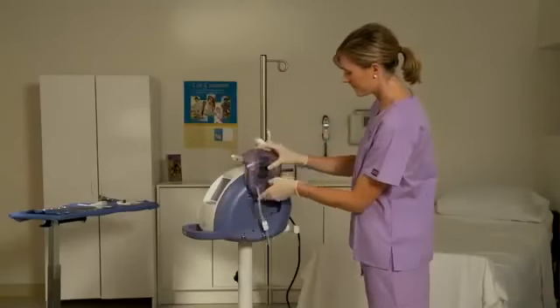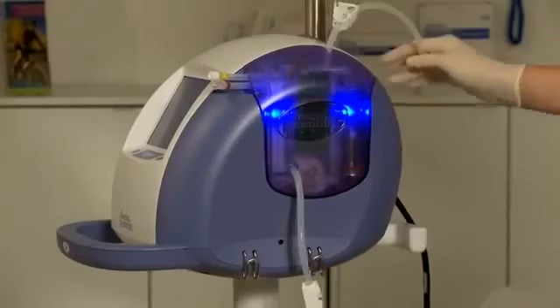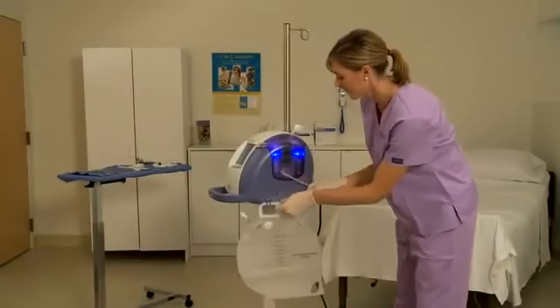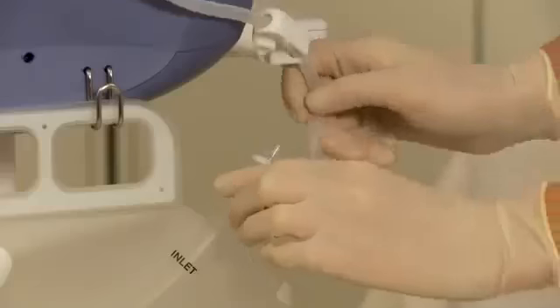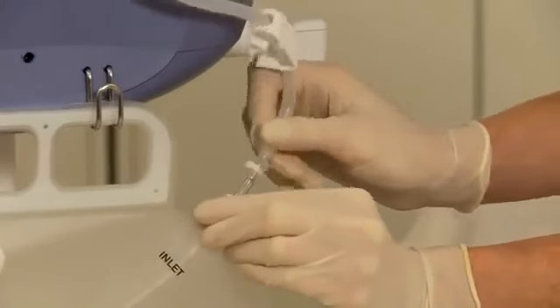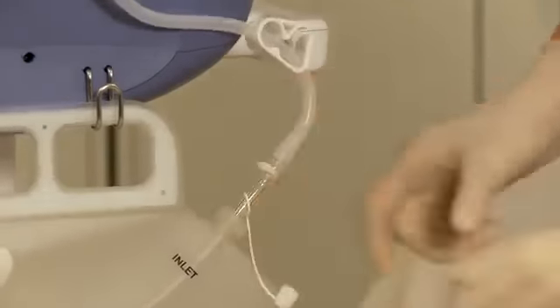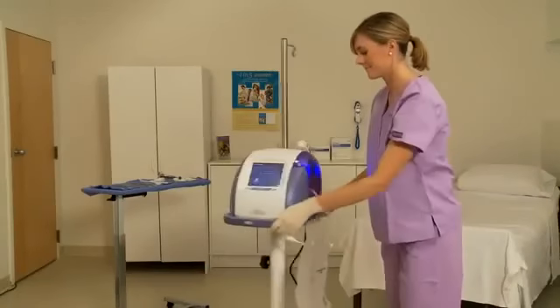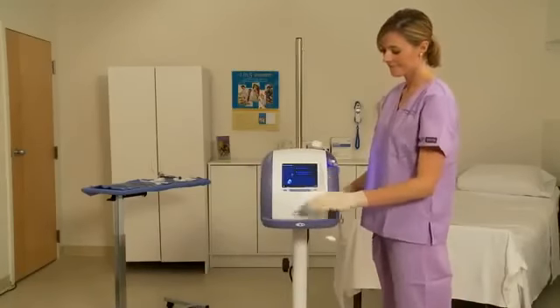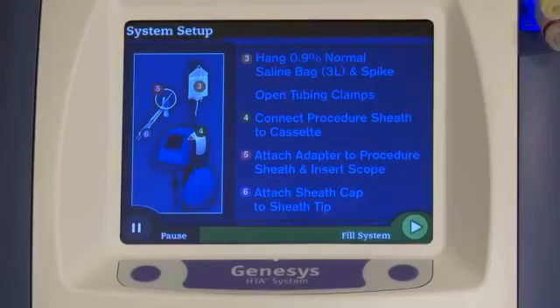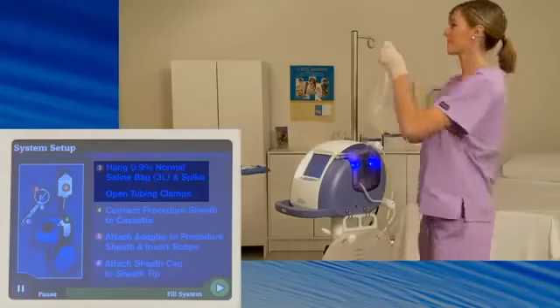Slide the cassette down until it is fully seated. 2 blue lights behind the cassette will illuminate. Hang the drain bag on the console and connect the drain line luer fitting from the cassette to the drain bag. Press the right-hand console button to engage the cassette. Once the system checks the cassette, the remaining setup steps will be displayed on the screen.